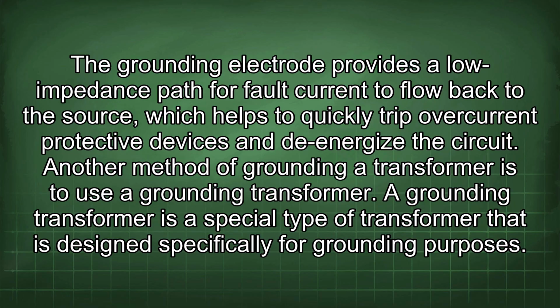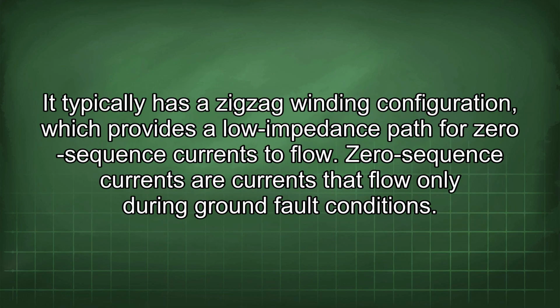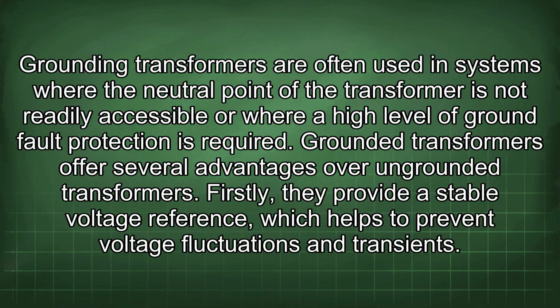Another method of grounding a transformer is to use a grounding transformer. A grounding transformer is a special type of transformer that is designed specifically for grounding purposes. It typically has a zigzag winding configuration, which provides a low impedance path for zero-sequence currents to flow. Zero-sequence currents are currents that flow only during ground fault conditions. Grounding transformers are often used in systems where the neutral point of the transformer is not readily accessible or where a high level of ground fault protection is required.